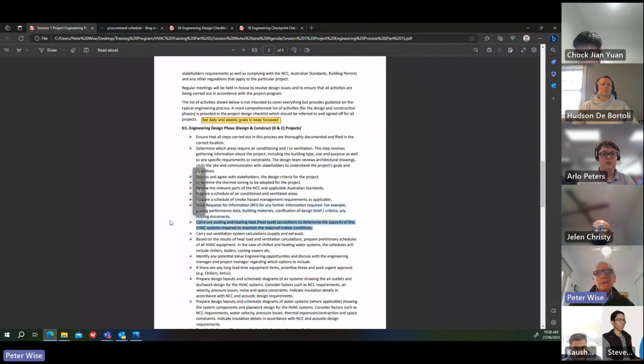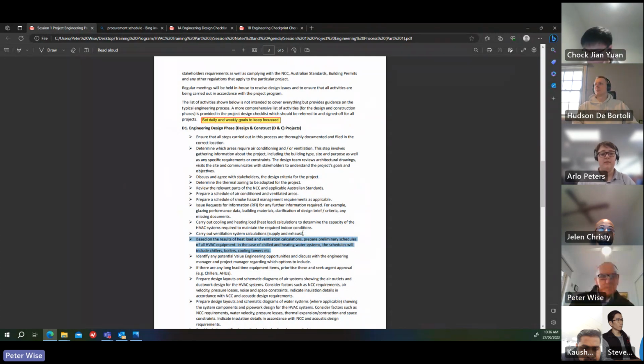You can carry out the cooling and heating load calculations to determine the capacity of the HVAC systems required to maintain the required indoor conditions. You can carry out ventilation system calculations for supply and exhaust, with reference to AS 1668 or whatever applies to the project. The ventilation might be stipulated in the design criteria—it should be—but if it doesn't comply with 1668, you have to comply with 1668. Based on the heat load and ventilation calc results, you can prepare preliminary schedules of all the HVAC equipment. For chilled and heating water systems, the schedules will include chillers, boilers, cooling towers, pumps, etc.